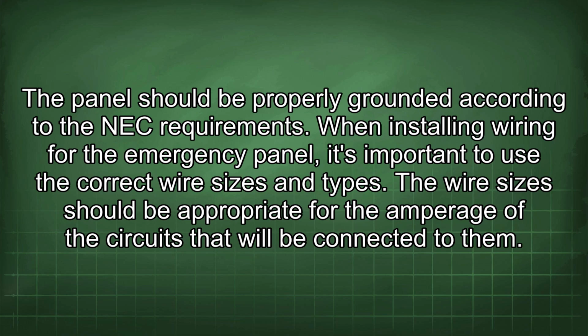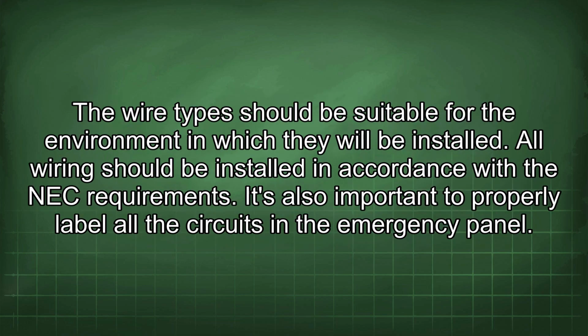When installing wiring for the emergency panel, it's important to use the correct wire sizes and types. The wire sizes should be appropriate for the amperage of the circuits that will be connected to them. The wire type should be suitable for the environment in which they will be installed. All wiring should be installed in accordance with the NEC requirements.